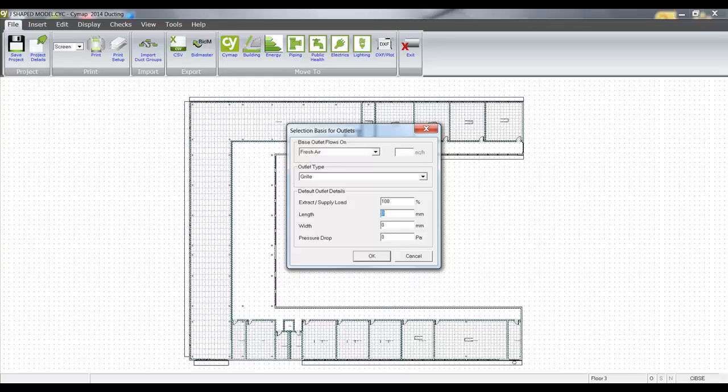We can, if we wish, fix our grill sizes. The program will size the next size for you if you don't put these sizes in. And also we can put a pressure drop across the grill.